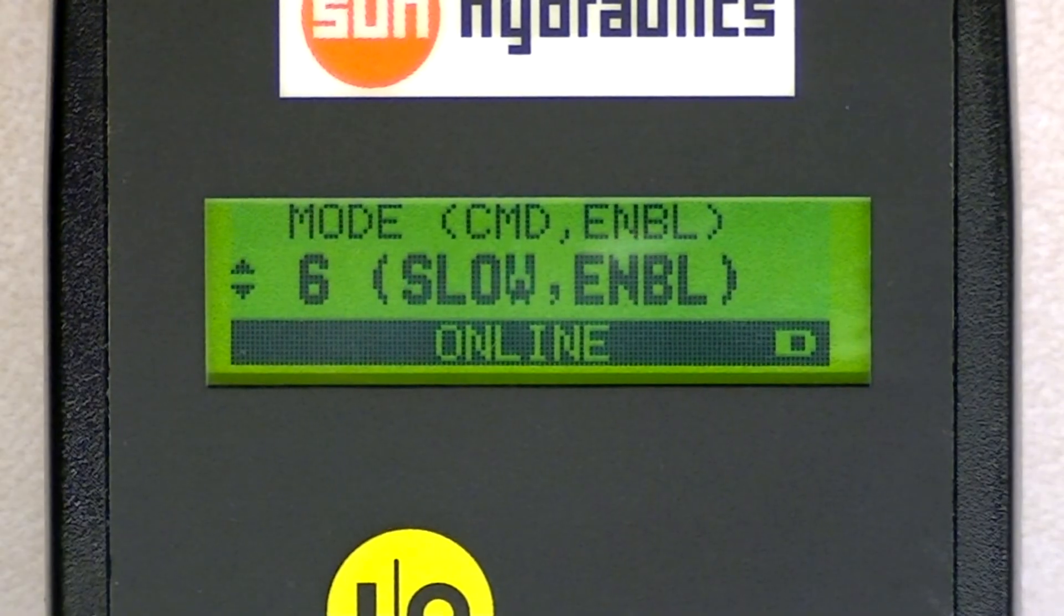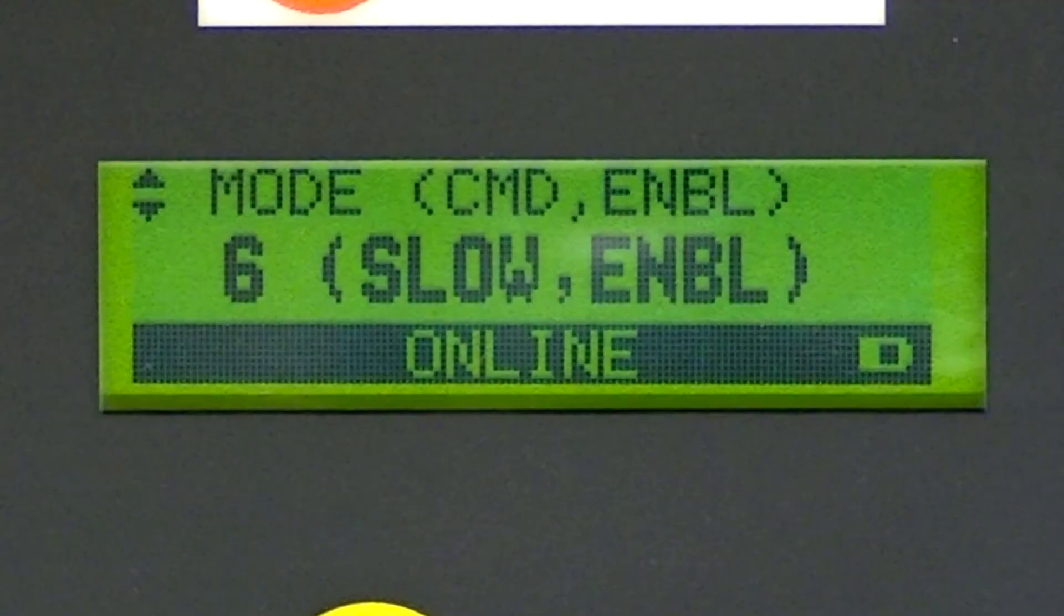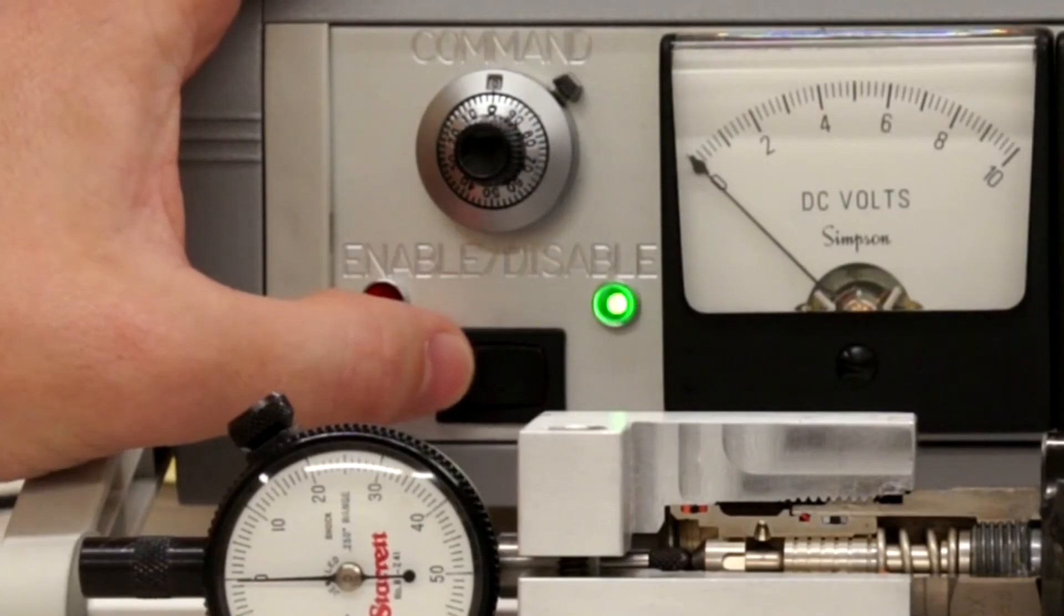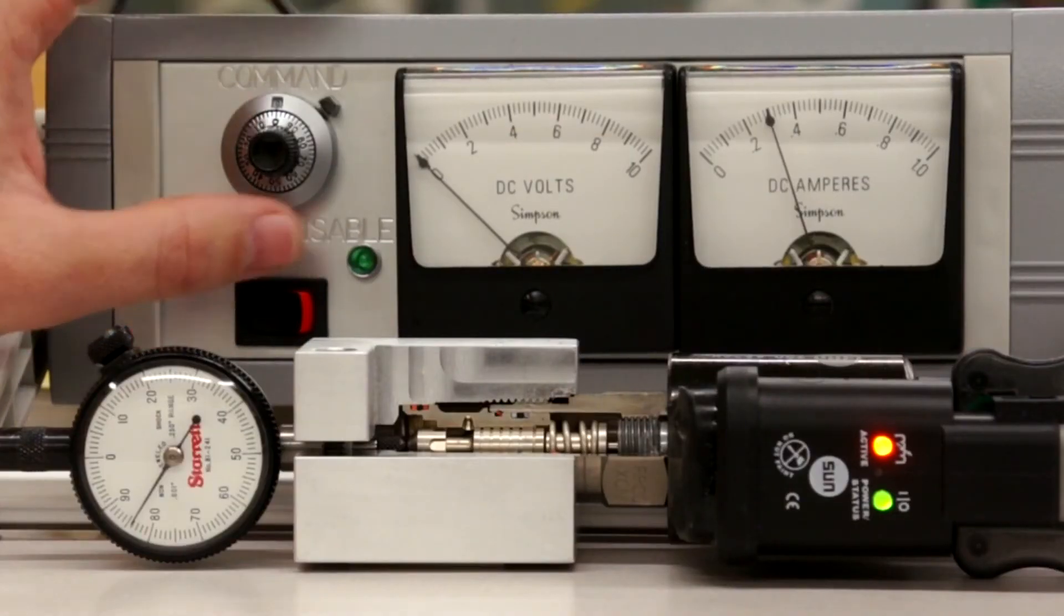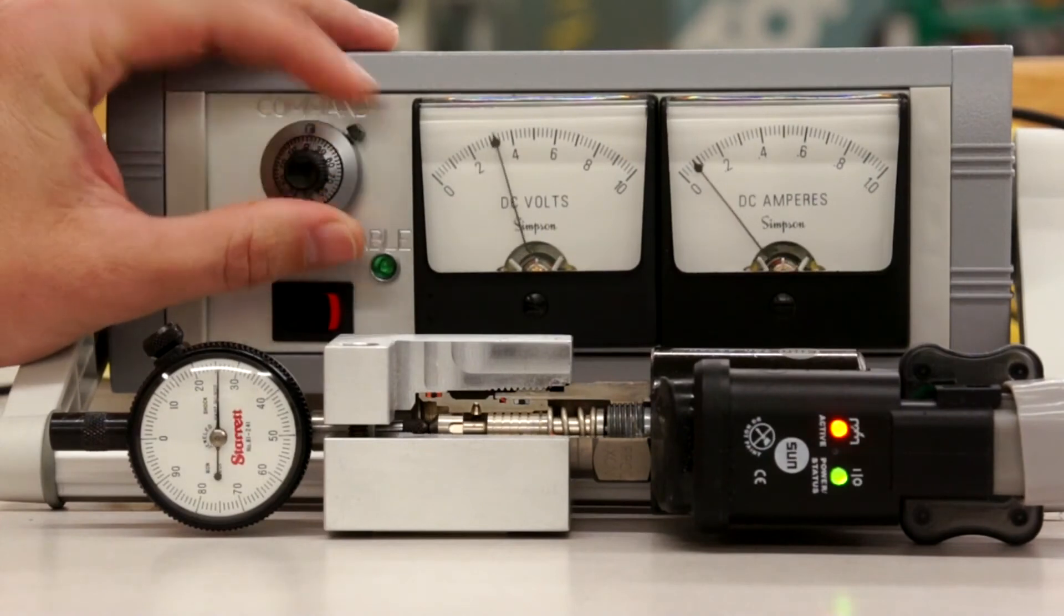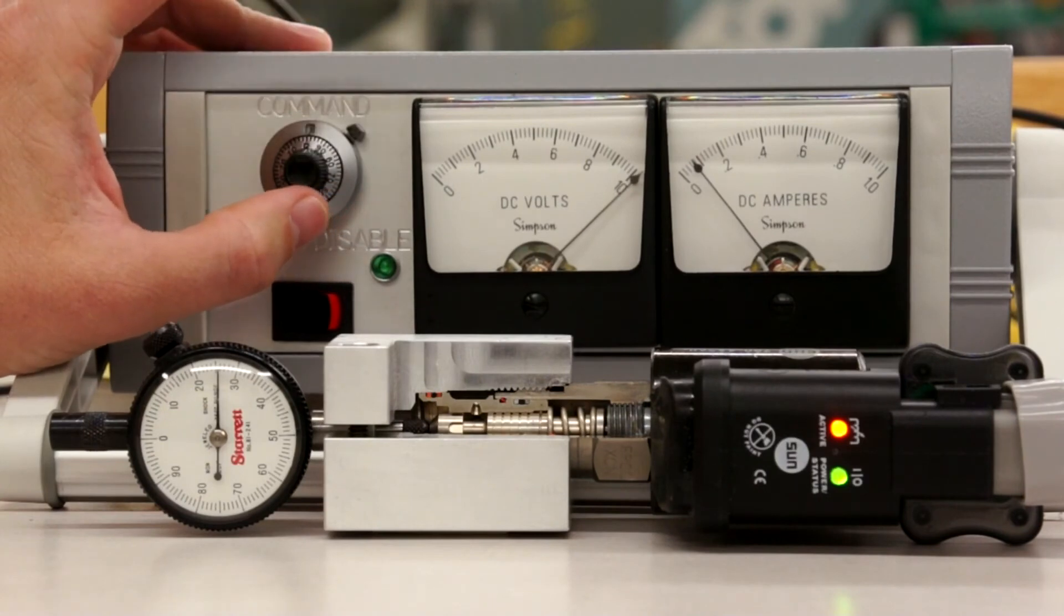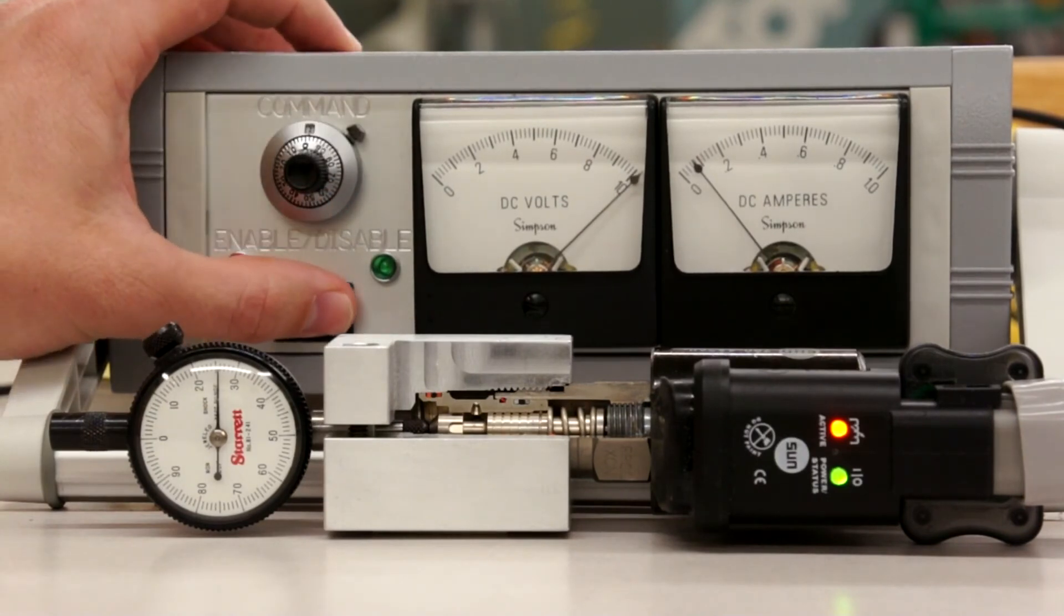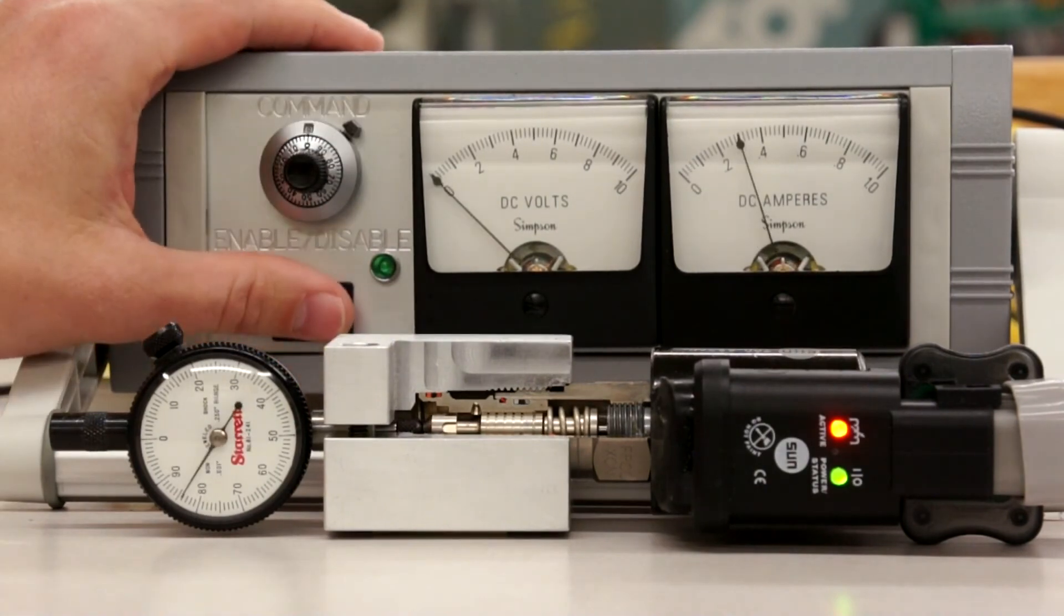Mode 6 is the same as mode 5, except it is inversed. Mode 6 is called slow, with an enable function. Turning on the enable gives you maximum output current, whereas in mode 5, it gave you minimum output current. The full command threshold is now from 2 to 10 volts, which gives you minimum output current. The 3 speeds again are off, minimum output current, and maximum output current.